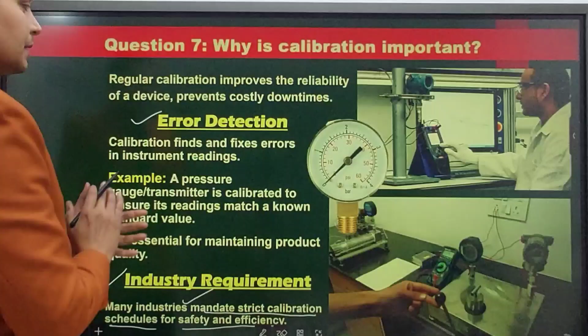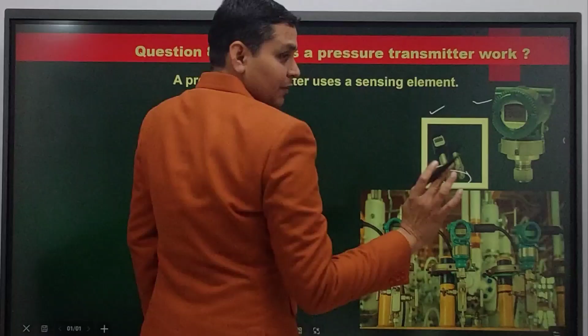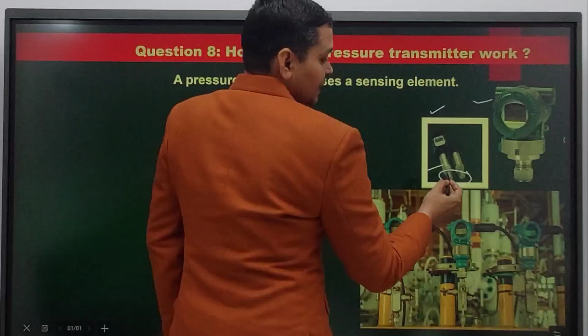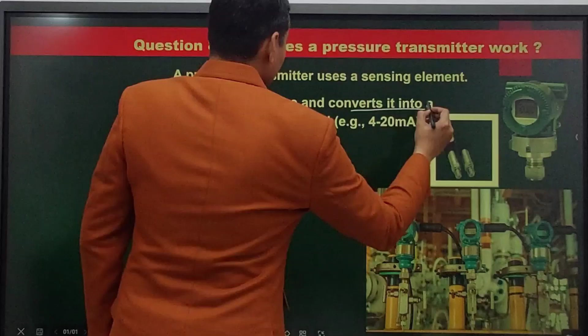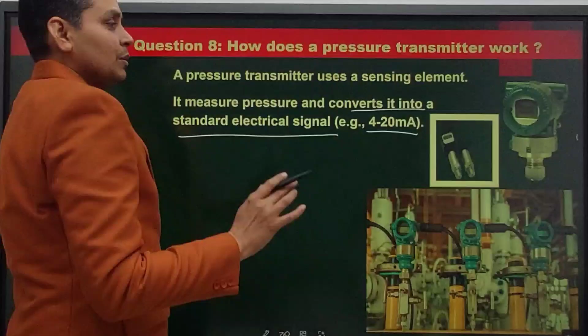And the next question is, how does a pressure transmitter work? A pressure transmitter uses a sensing element. Here you can see, friends, these are the pressure transmitters and here it is a sensing element. They use diaphragm for sensing the pressure. This type of pressure transmitter, pen type pressure transmitter, you can see diaphragm here, and this type of pressure transmitter also uses diaphragm here. Pressure transmitters measure pressure and convert it into a standard electrical signal. Here, one thing you need to know that it converts into a standard electrical signal. That means 4 to 20 milliampere.